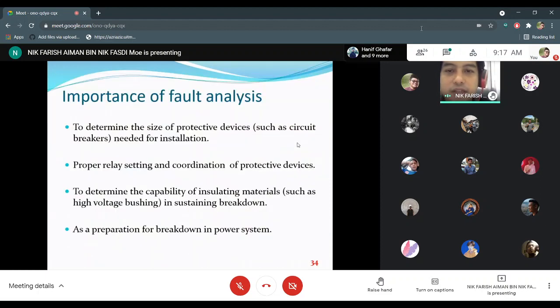Importance of fault analysis: to determine the size of protective devices such as circuit breakers needed for installation, proper relay setting, and coordination of protective devices. This is why fault analysis is important - so we know what rating of circuit breaker to use.